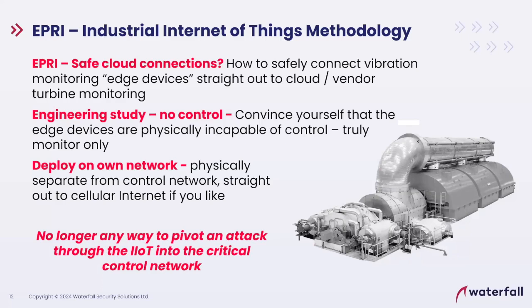Now, what's the worst that can happen? You can compromise the devices. You can maintain your systems suboptimally. It'll cost you a few $1 million. You can buy insurance for that. You have not put the entire control system at risk by carving a connection from the control system out to the internet. This is an example of network engineering. It's a way to do what otherwise might seem a very dangerous thing safely, because you've engineered the networks in such a way that a compromised edge device physically has no advantage in terms of compromising the rest of the control system because it's connected to a different network.